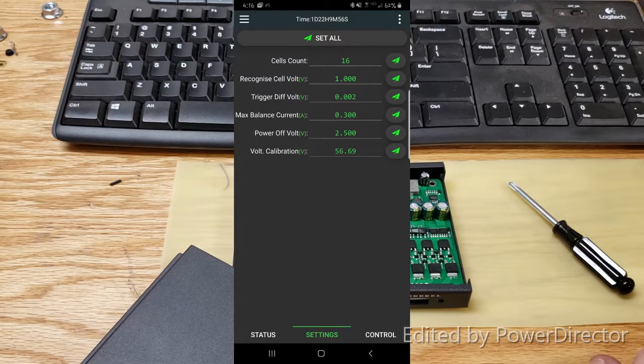Trigger differential voltage, you can go down as low as 0.002, meaning 2 millivolts, and at 2 millivolts it will trigger balancing. Maximum balance current, I have it down at 0.3 amps or 300 milliamps, it will go up to 1. Next setting is power off voltage.